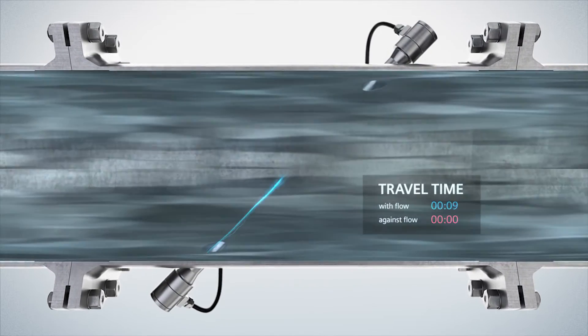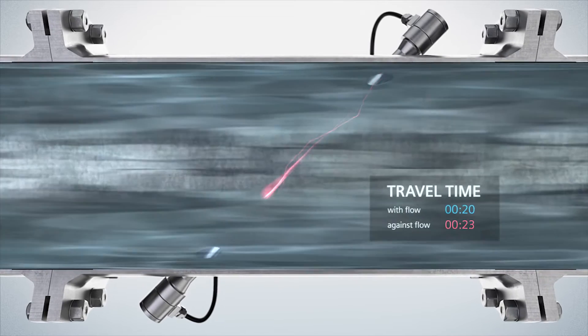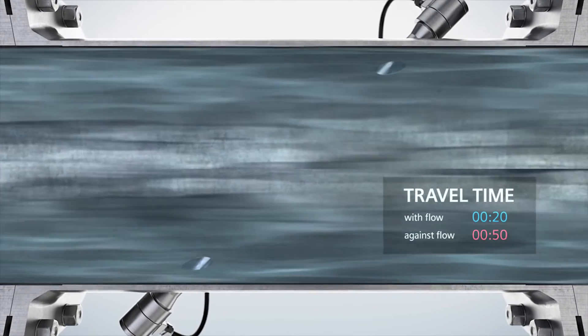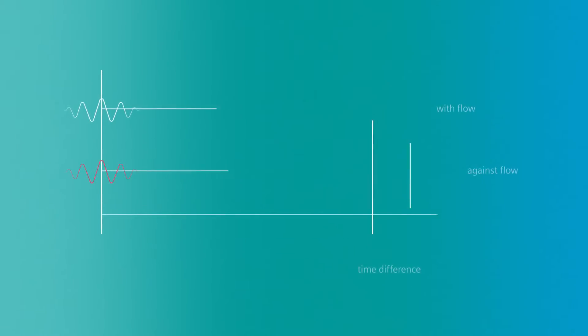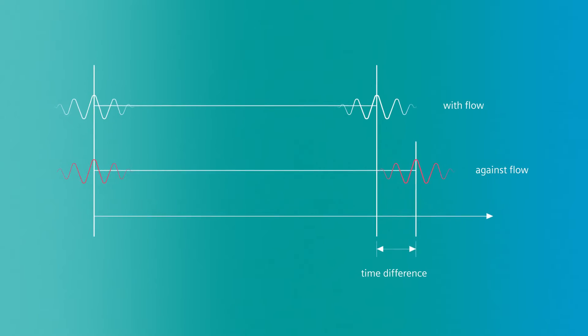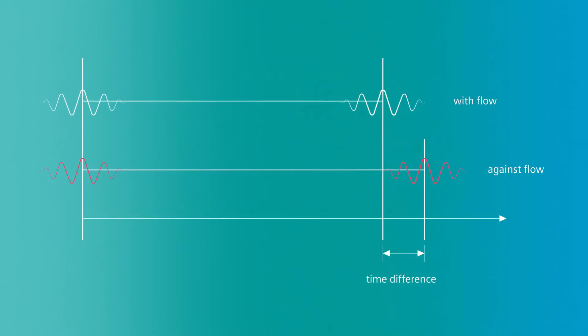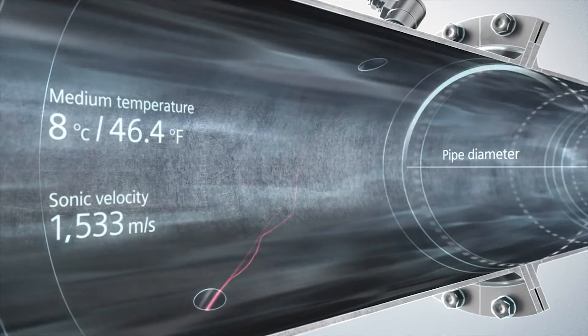When moving in the same direction as the flow, they travel faster than waves traveling against the direction of the flow. The higher the flow velocity of the medium, the greater the difference between the two transit times.